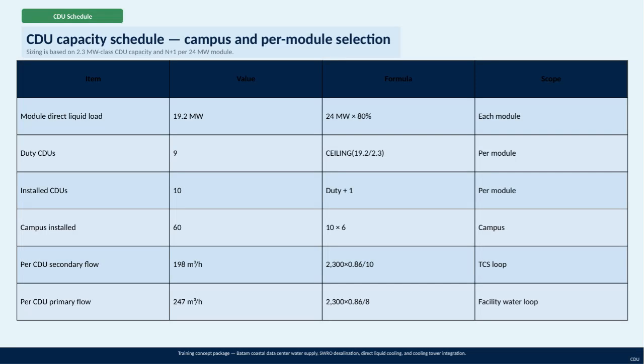Here we have the CDU capacity schedule, which is organized both at the campus level and per individual module. The sizing is based on a 2.3 megawatt class CDU capacity with an N+1 redundancy for each 24 megawatt module to ensure reliability. Starting with the module's direct liquid load, it's set at 19.2 megawatts, which is 80% of the 24 megawatts capacity per module. To handle this load, 9 duty CDUs are required, calculated by dividing 19.2 by 2.3 and rounding up.